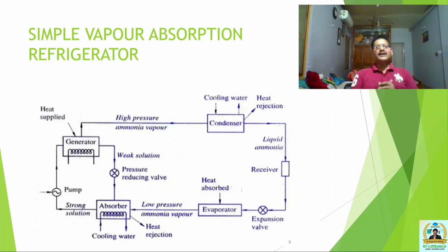You may employ steam or a heating coil for that purpose. So, the strong solution gets heat from the heating coil. As a result, the ammonia leaves the solution, leaving behind hot weak solution of Aqua-Ammonia. We call it weak solution because it contains comparatively lesser amount of ammonia.